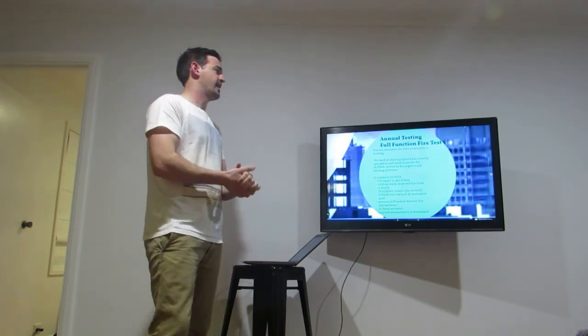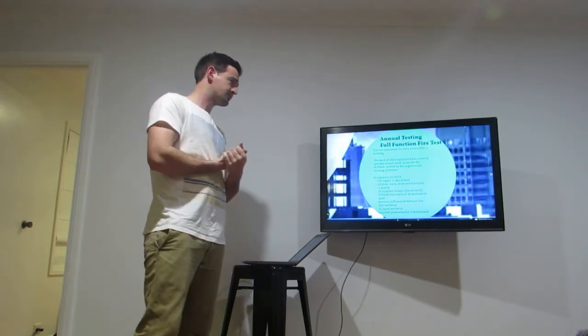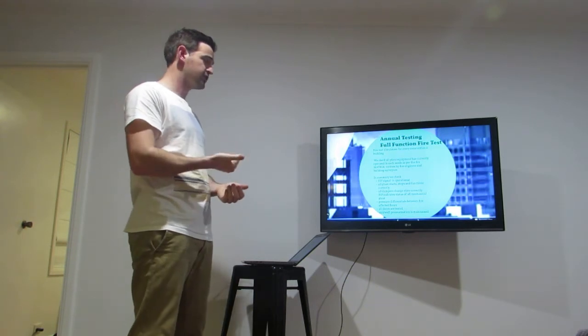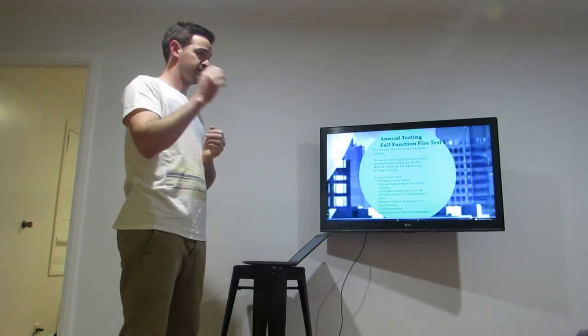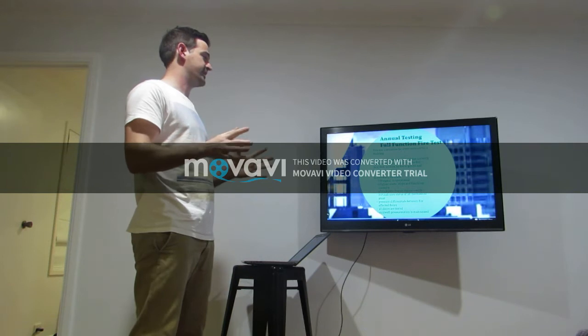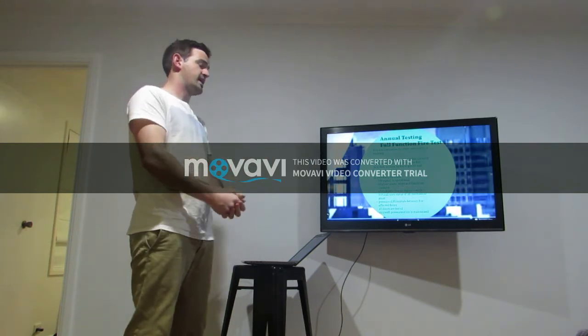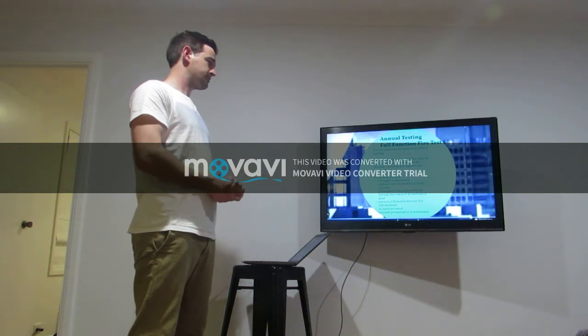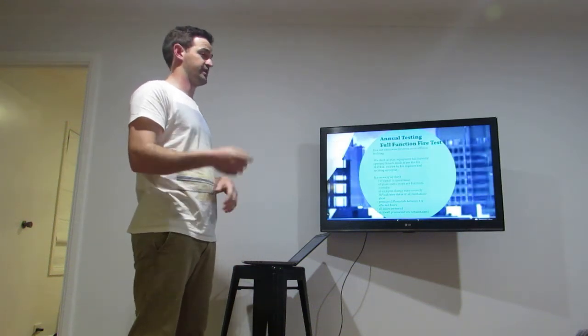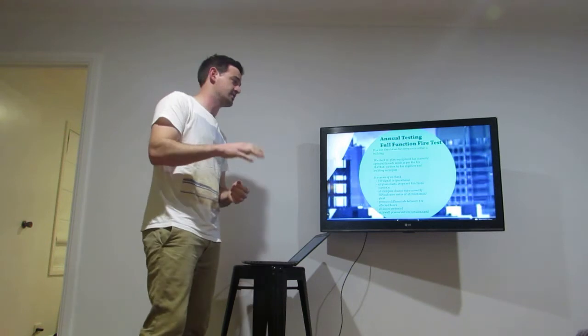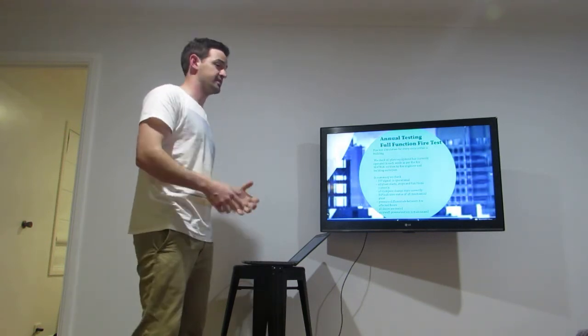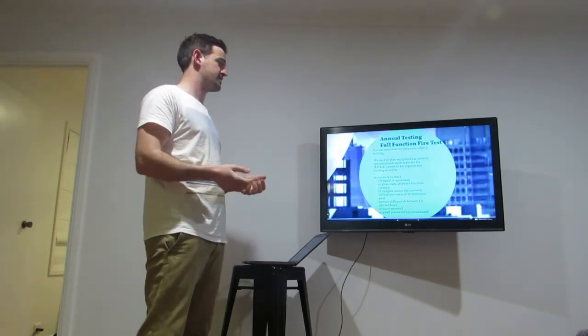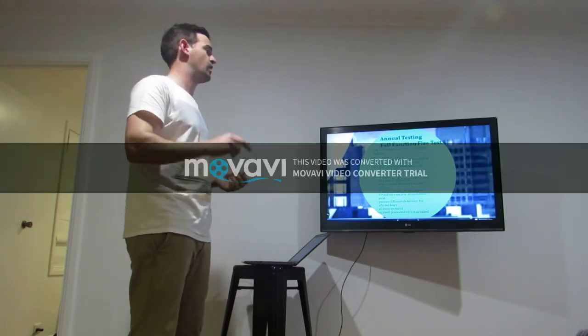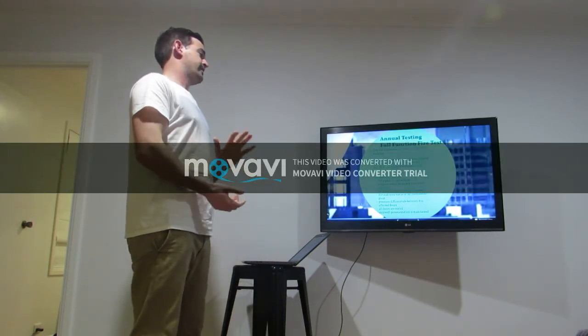So in summary, on an annual fire test, we check the signal from the FIP is operational and that it's sending out to the plant exactly what we need to happen. We need to make sure the plant starts and stops and functions correctly. We need to check all dampers change state in fire and in pressurization. This is a visual check of the blades themselves. This can be very time consuming, as sometimes there are up to a couple of hundred dampers that need to be individually checked twice.